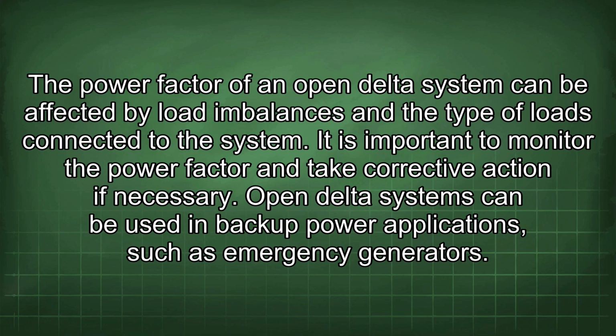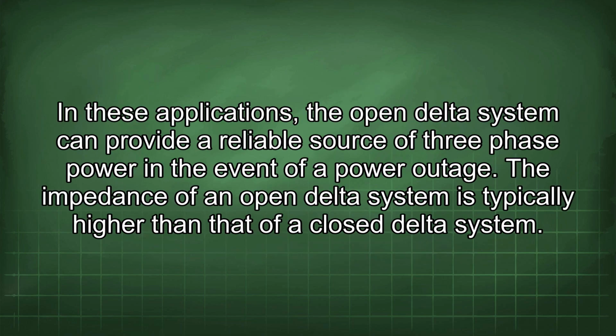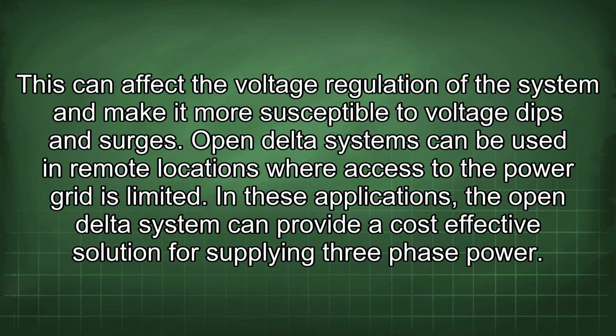Open delta systems can be used in backup power applications such as emergency generators. In these applications, the open delta system can provide a reliable source of three-phase power in the event of a power outage. The impedance of an open delta system is typically higher than that of a closed delta system. This can affect the voltage regulation of the system and make it more susceptible to voltage dips and surges.